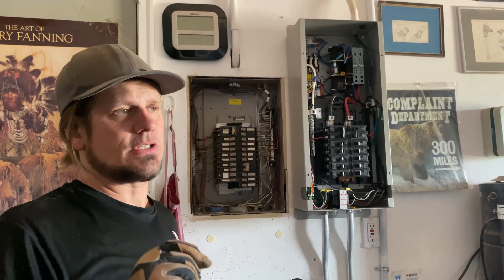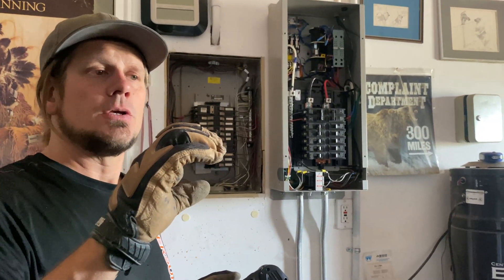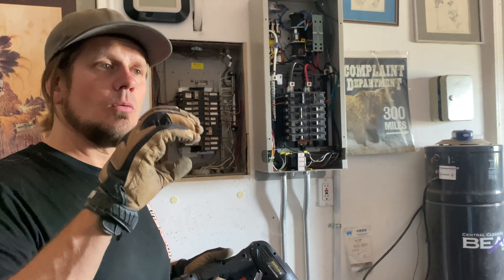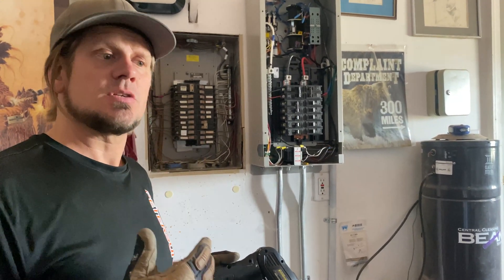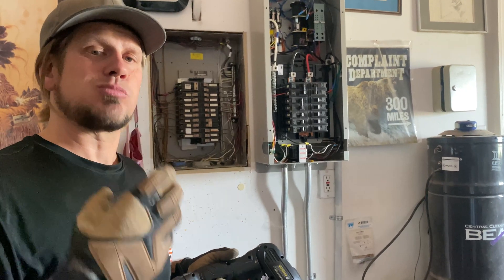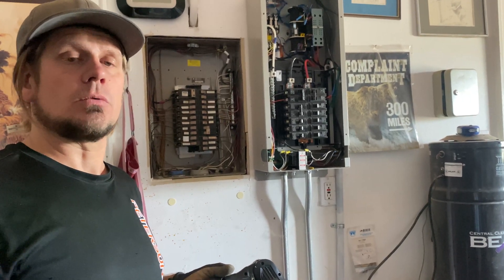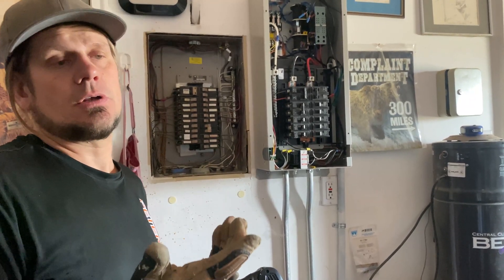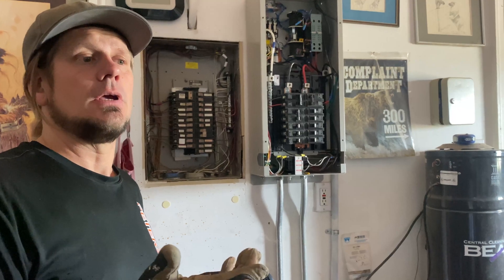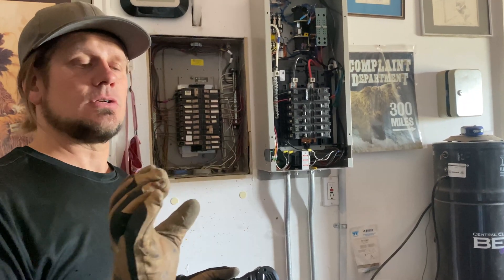A lot of well guys will know this — it's like a little buck boost that goes up to 463 volts with the capacitor. We checked the microfarads and the capacitor was at 164 to 172, which appears fine. So my thinking is the weakest link that broke here is maybe the float switch. Those float switches are 240-volt rated; there is no ground. On the line side of the float switch it's fairly strong at 117-118 volts, but on the back side it was only 60 volts. He's got three floats — a low, a medium, and a high.